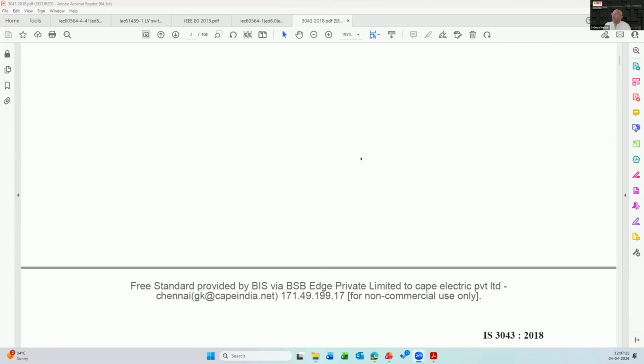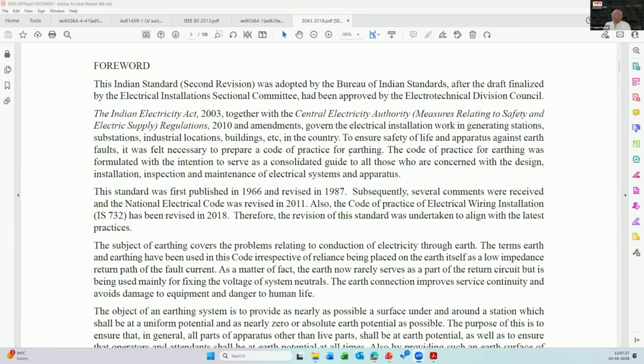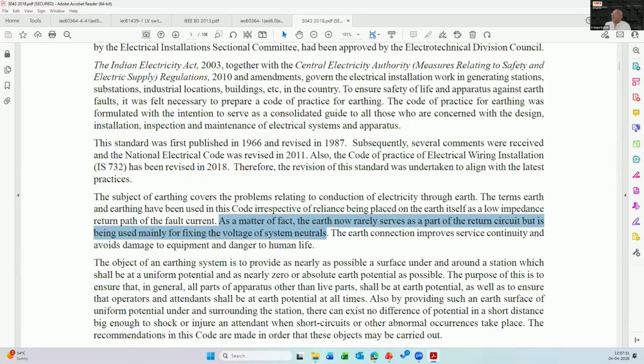So this is the standard. At the introduction of the standard itself, it's very clearly written. Here is the foreword: as a matter of fact, the earth now rarely serves as a part of a return circuit. That means the earth electrode in soil is not to carry current as a part of a return circuit, but is being used mainly for fixing the voltage of the system neutrals. The earth electrode is used to fix the voltage of a system. It is not a current carrying part through which you can inject some current.